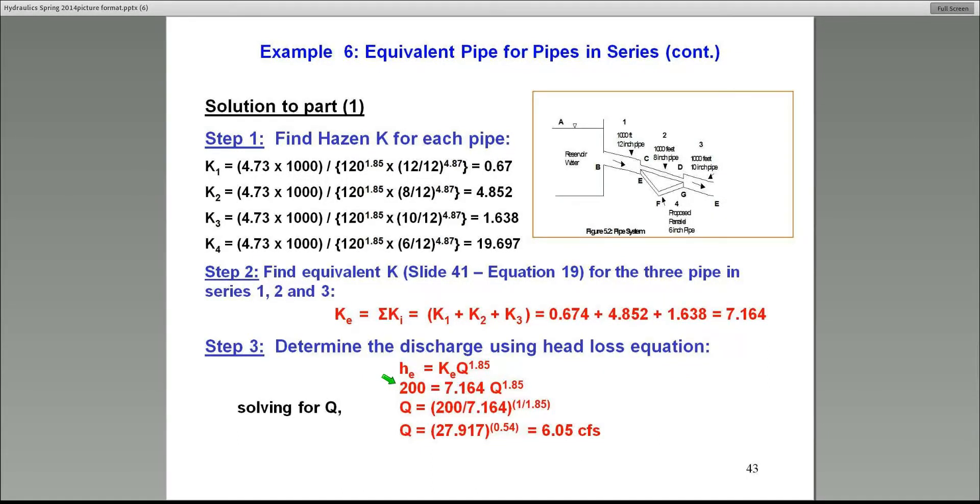To solve for the flow, we simply use this equation. The head loss is equal to KE Q to the power 1.85, which is the equation I showed you earlier for friction loss. Invert that equation to solve for Q. In this case, it comes out to be 6.05 CFS. It's easy to calculate the flow rate given that head loss of 200 feet.